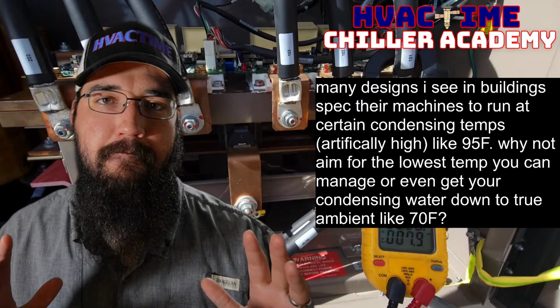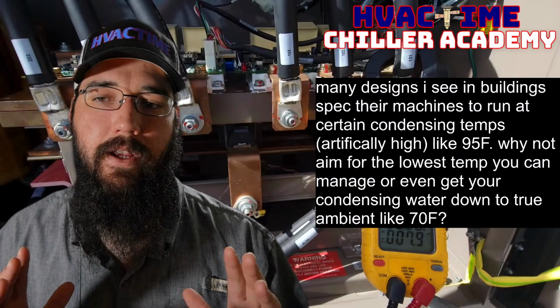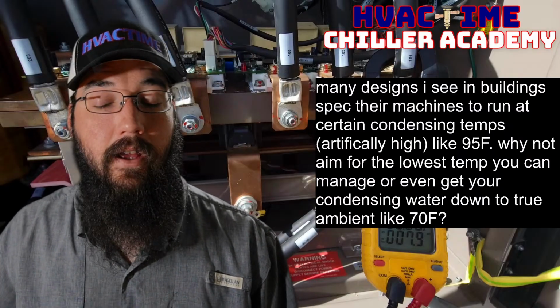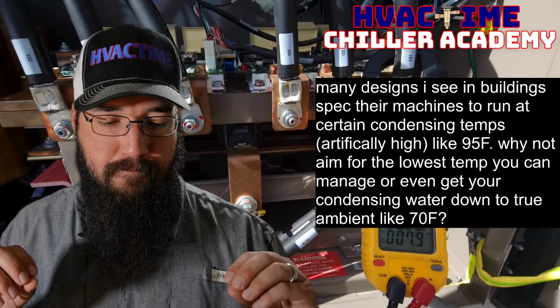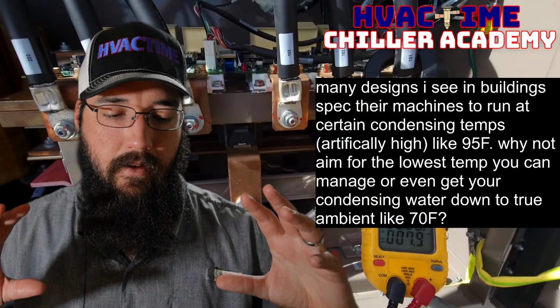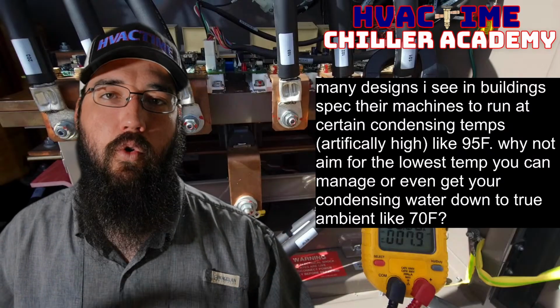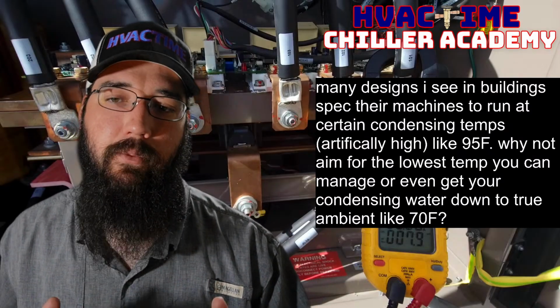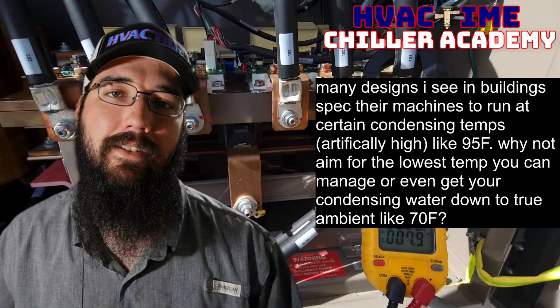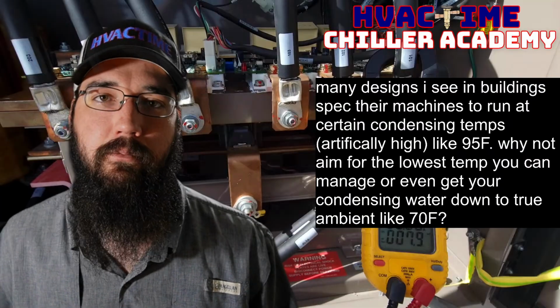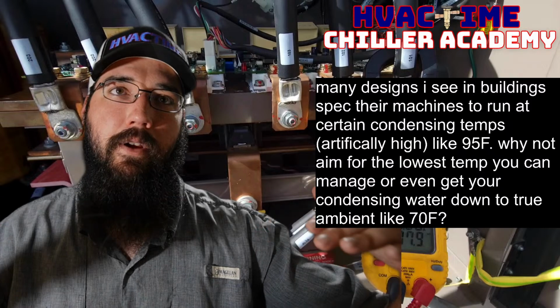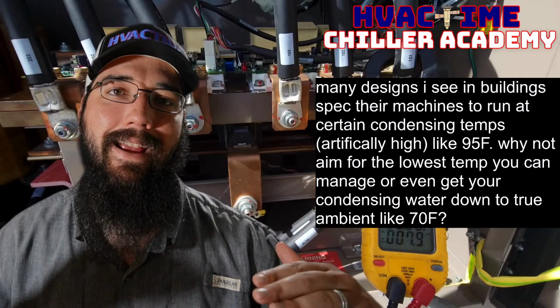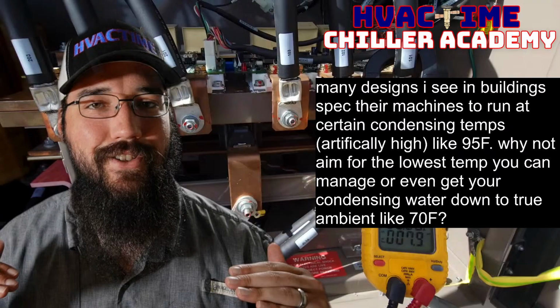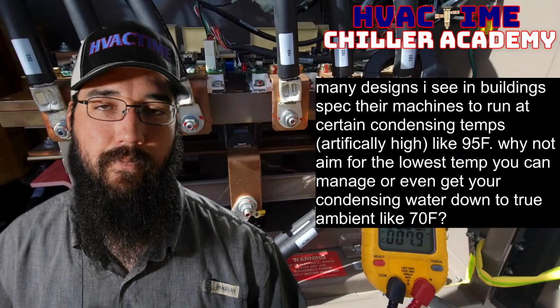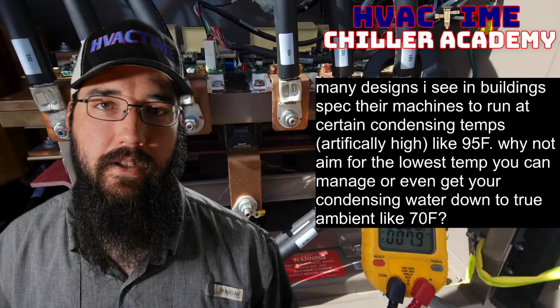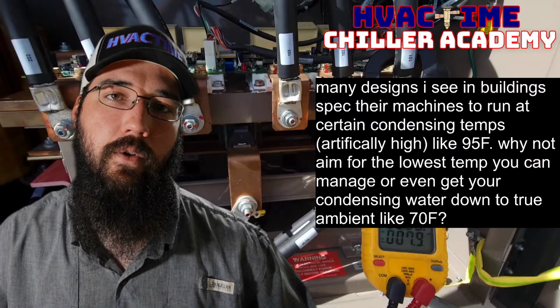Here's my approach to this and the pitch that I would give. Our ultimate goal for condenser water, given the fact that we have condenser water temperatures, means that we've got a water cooled system, period. Our goal, in my opinion, should be to try to maintain as low of a condenser water temperature as that chiller is allowed to handle, and do that as effectively as we can so that we can lower the amps.